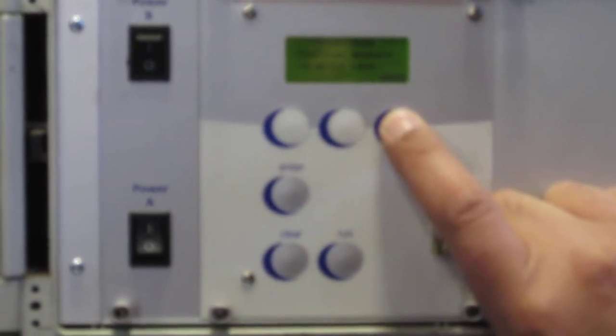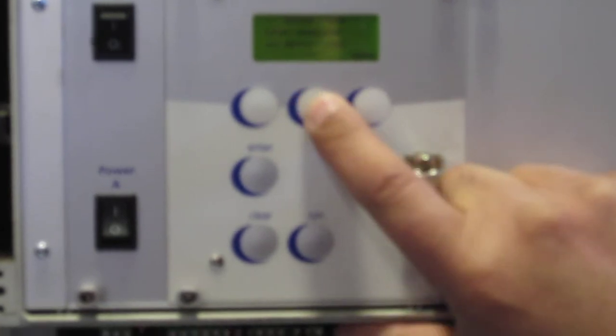So we'll say more. In case of an error, we've got it set to continue. Once again, you have this little cursor button, continue, stop, measure. We want to continue the measurement. So if it goes into error, it holds that measurement. Then after the way we have it set for a certain milliamp out, as soon as the error goes away, it continues measurement instead of holding that measurement, and you happen to come out and push enter.